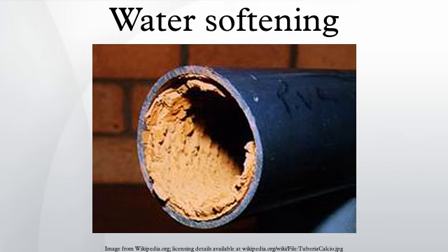Regeneration of ion exchange resins. When all the available Na+ ions have been replaced with calcium or magnesium ions, the resin must be recharged by eluting the Ca2+ and Mg2+ ions using a solution of sodium chloride or sodium hydroxide, depending on the type of resin used. For anionic resins, regeneration typically uses a solution of sodium hydroxide or potassium hydroxide. The waste waters eluted from the ion exchange column containing the unwanted calcium and magnesium salts are typically discharged to the sewage system.